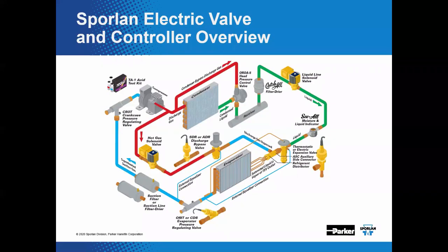Now, here's how some of these other applications would appear in the vapor compression refrigeration system. If you take a look here, you'll see right here an SDR valve that could be used in place of a traditional hot gas bypass valve in a hot gas bypass or discharge bypass application. We've been talking here about the EEV for superheat control, and we could also go down the path of talking about evaporator pressure regulation via a CDS valve as opposed to an ORIT or a SORIT or a Sporlan valve. In subsequent webinars, we'll discuss these different applications.